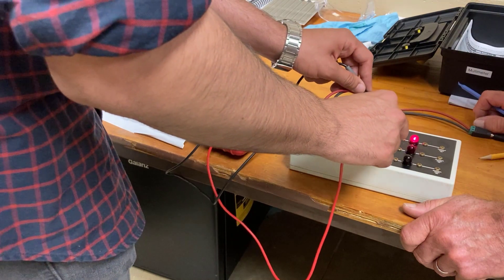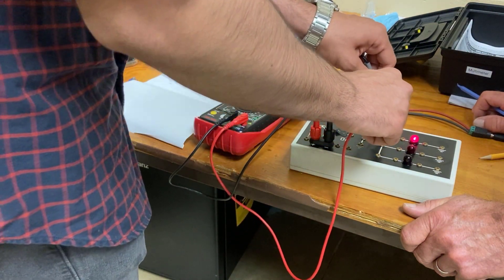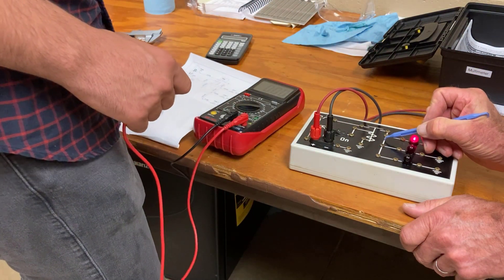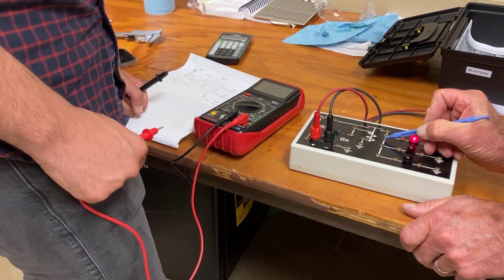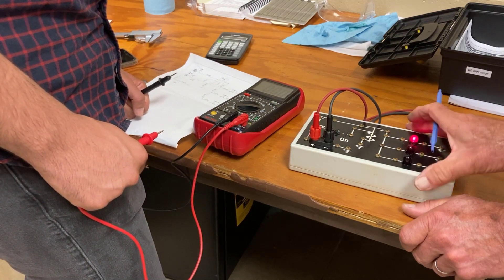Zero. That one measures zero because it's good. Measure from here to here. You'll get 12 because that's the bad wire. You'll get a 12 volt reading.